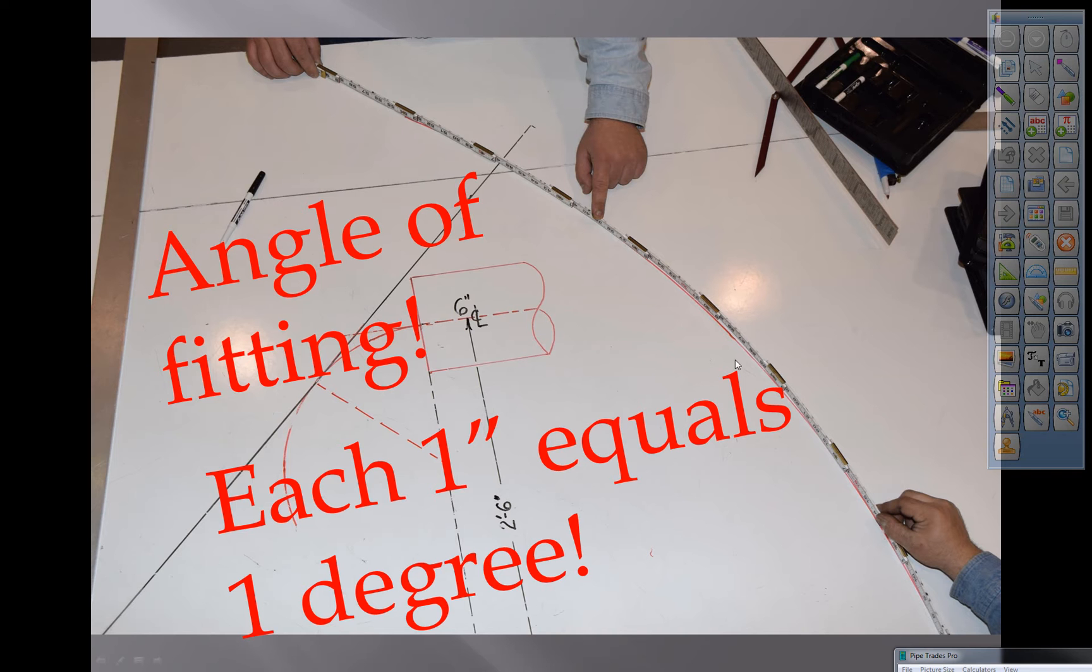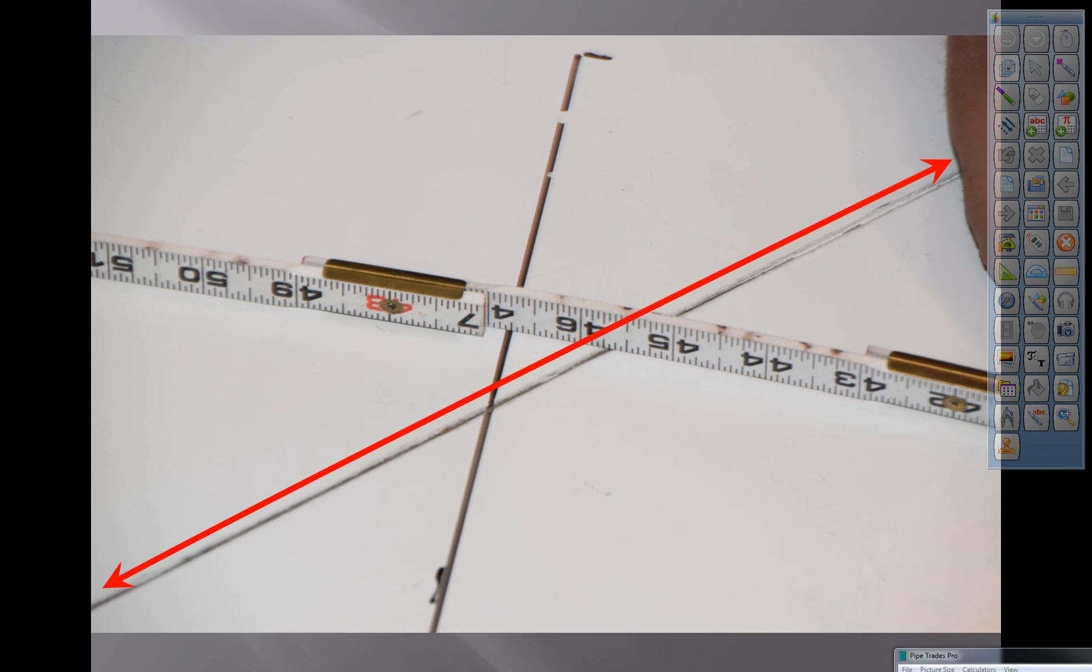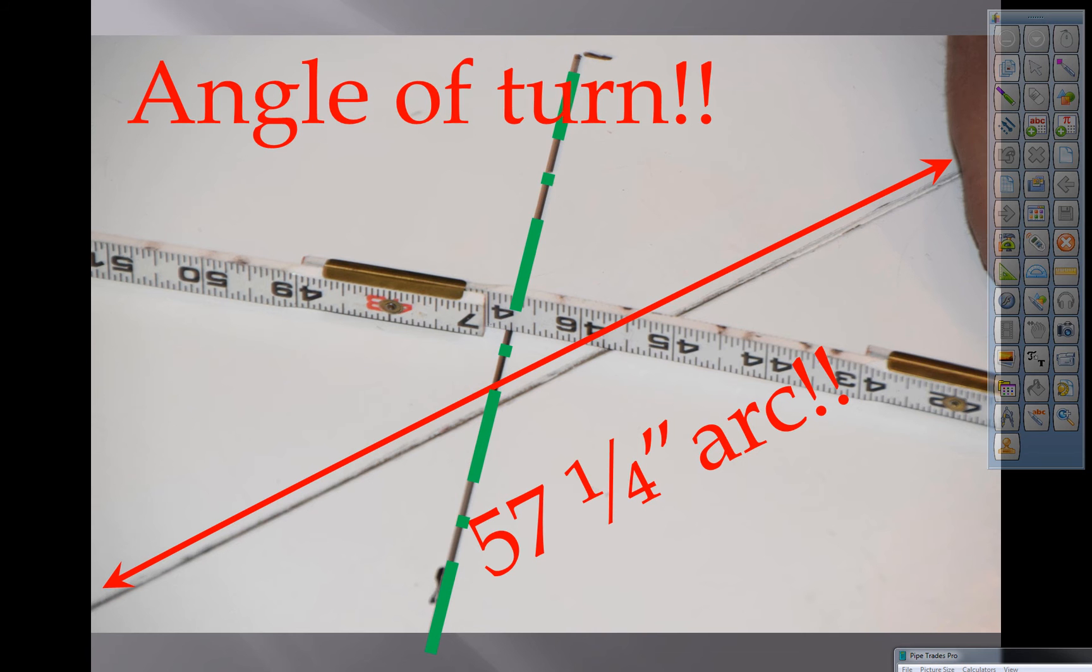That's the point we need to read. There's our 57 and a quarter arc. The green was our angle turned. So you can see we have 46.75. So that is our angle of fitting. 46 and 3 quarters out of a 6 inch long radius 90. So we know the fitting takeoff is 3 and 7 eighths.